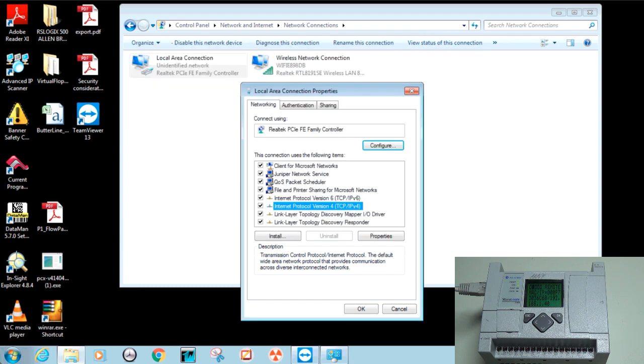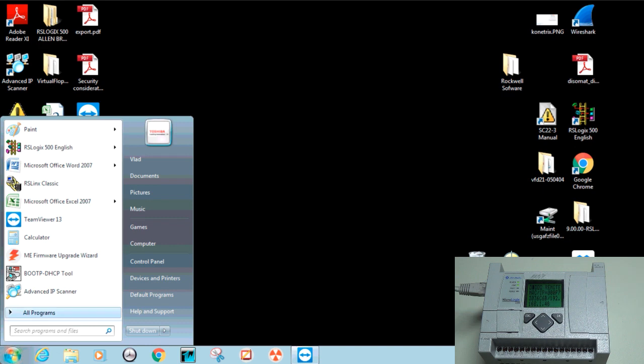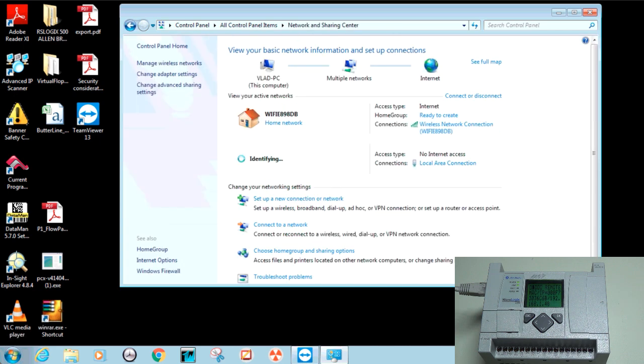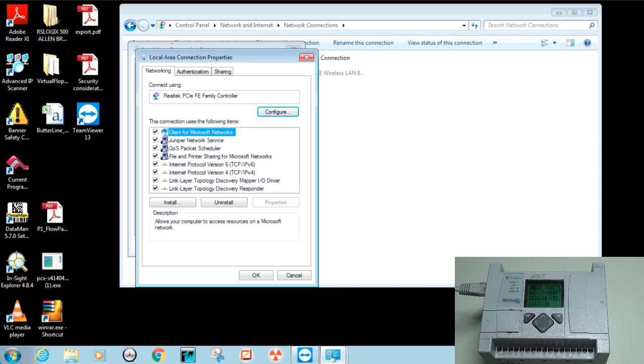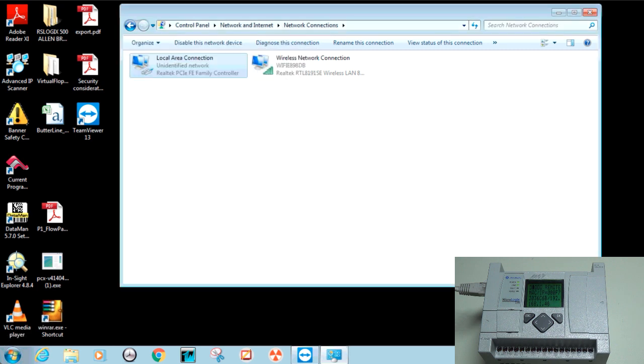Now that we're connected, go back into Control Panel, Network and Sharing Center, Change Adapter Settings, select Local Area Connection, go into Properties, and we need to be on the same network as the PLC — that's 192.168.1.x. Give the computer a different IP address than the PLC; I'll use 200, but any last octet not already used on that network will work. Hit OK and double-check that the setting took.